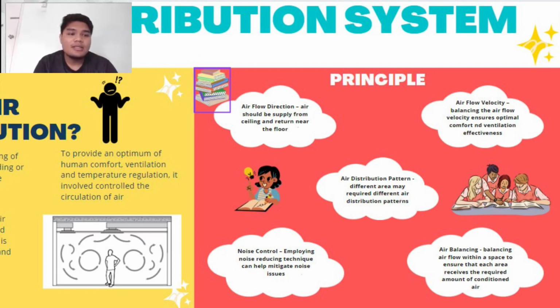Third is air distribution pattern, which means different areas may require different air distribution patterns. The air distribution pattern should consider the specific space when designing a system. Next is noise control, where employing noise reducing techniques can help mitigate noise issues, such as applying a silencer to reduce noise. Lastly is air balancing, which is balancing airflow within a space to ensure that each area receives the required amount of conditioned air.